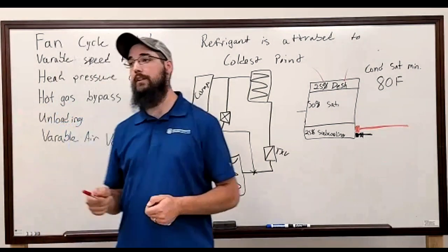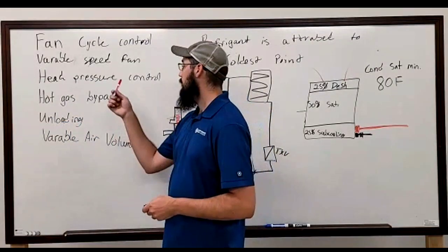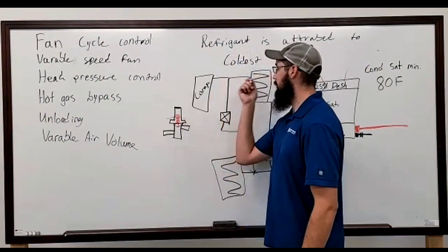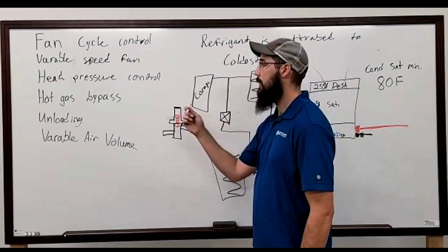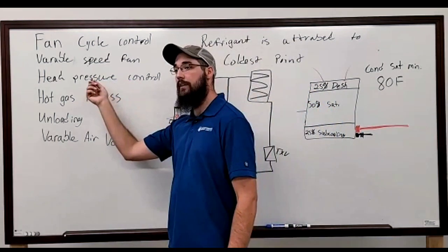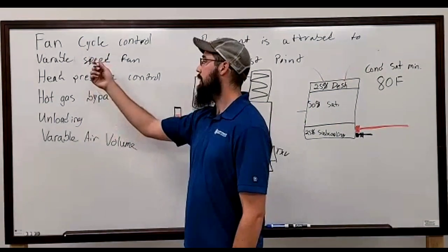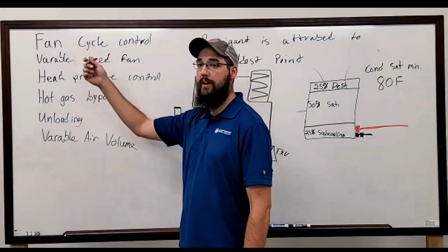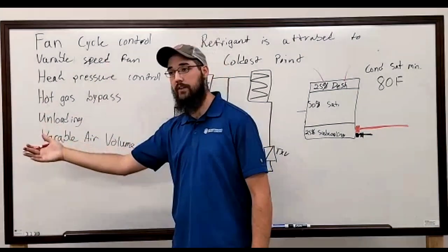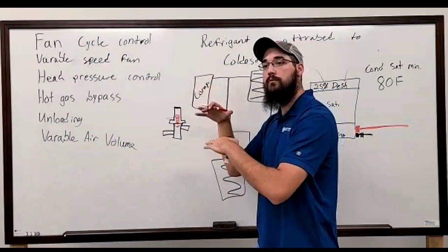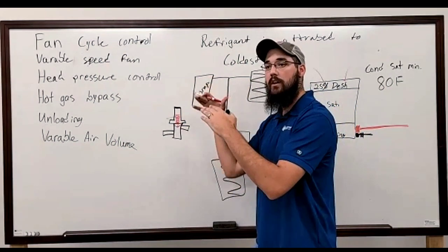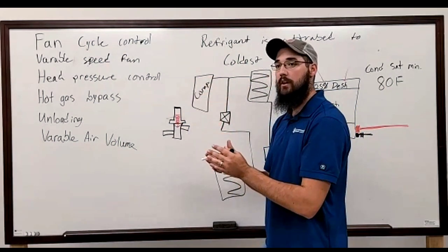On the condenser fan motors, yes. So, again, this is going to cause your head pressure to want to drop, because you're bypassing the condenser coil. And when the fans see that head pressure drop, the logic in the fans will respond and start cycling the fans accordingly. But this is where the whole thing is tuned in. It's got to work together.